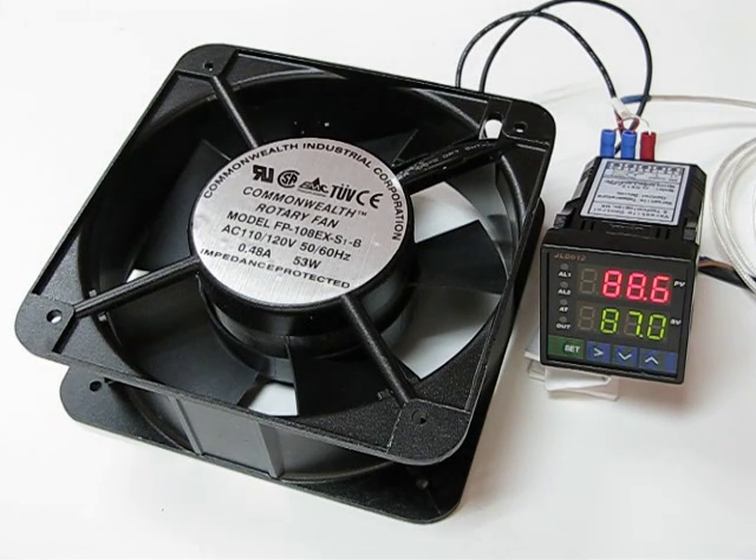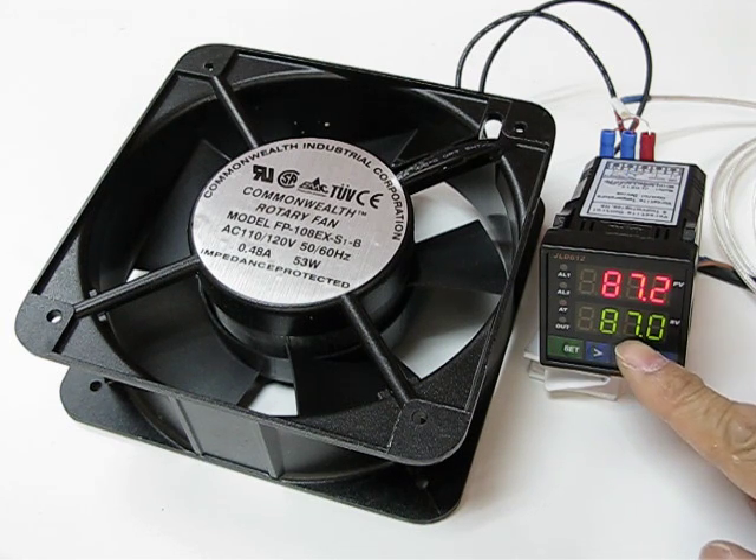Hello Mark, I'm doing another experiment for you with an AC110 cooling fan as the load. When you look at the temperature controller now, the current temperature is 87 and it keeps dropping down until it reaches 85, and it will trigger J2 and turn on the fan. Our set point is 87.